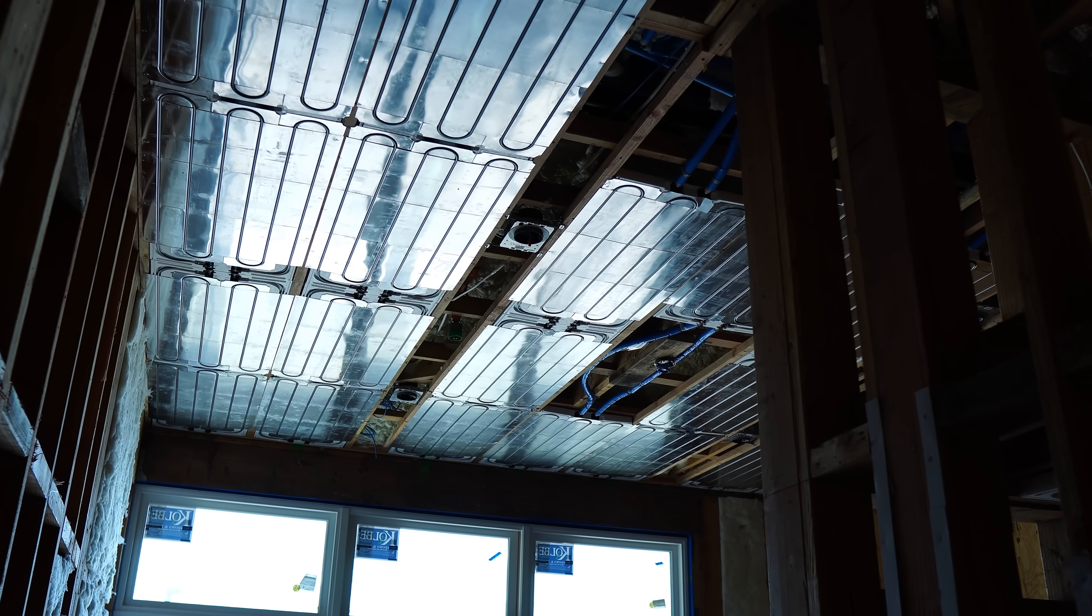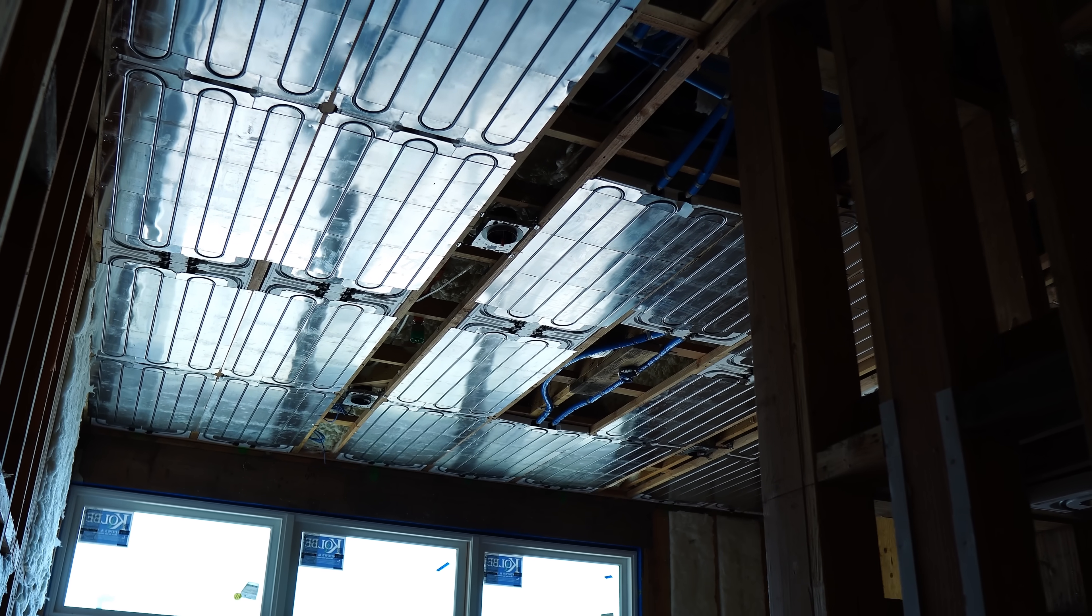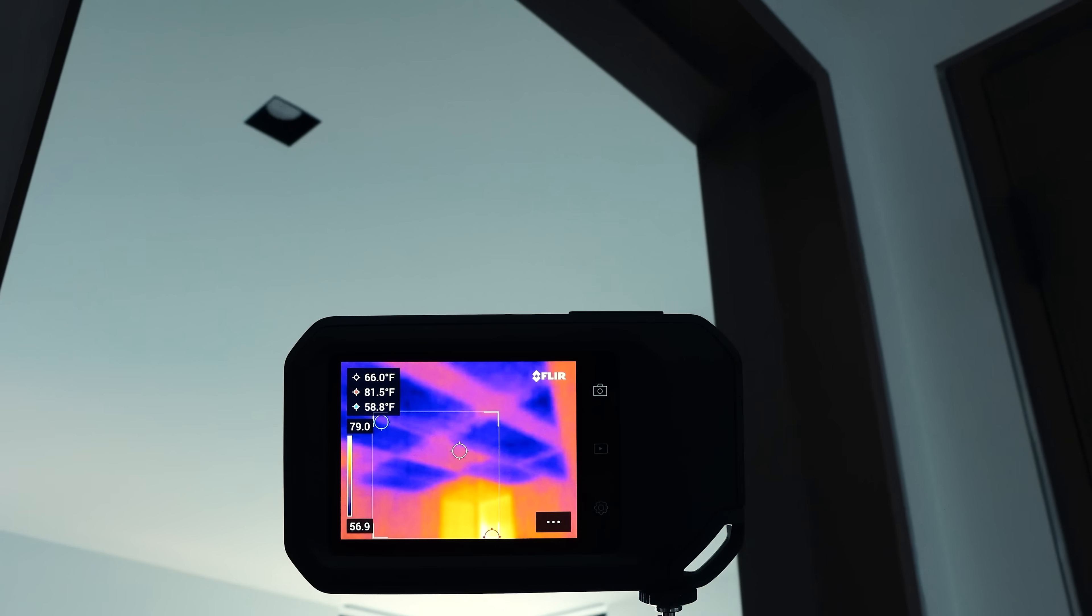When it comes to radiant cooling, you need a really low mass panel, which gives you a fast response time. We're also able to get more output via a radiant ceiling compared to a radiant floor. You're also getting an unobstructed radiant surface. With a radiant floor, you're covering it with carpet, furniture, stuff that absorbs thermal energy and might inhibit its performance. Whereas with a radiant ceiling, you're creating an unobstructed radiant surface. You don't have to worry about anything covering it, so that thermal radiation is really being transferred to the objects and occupants below.